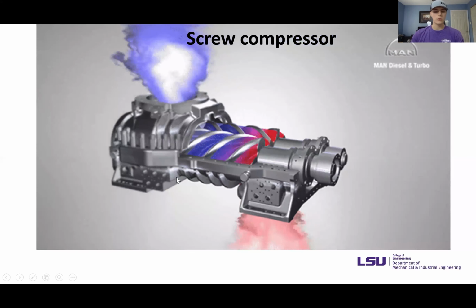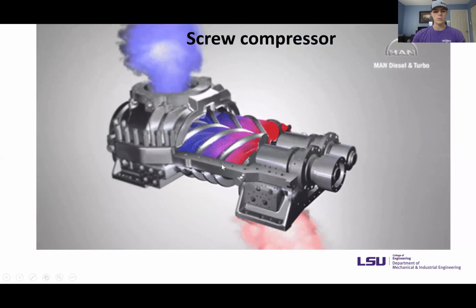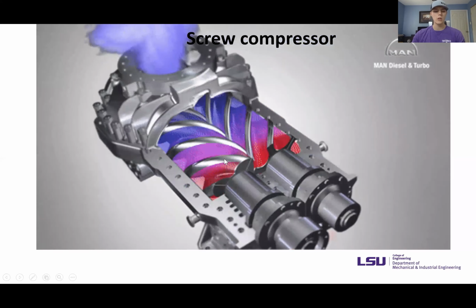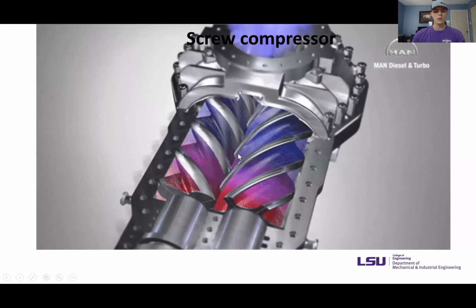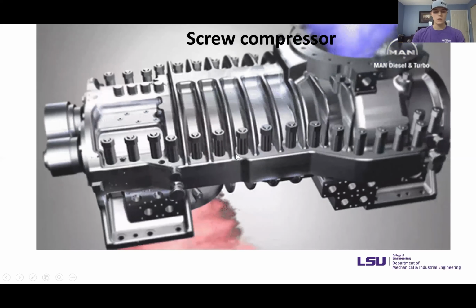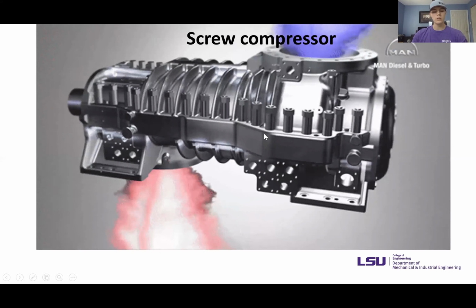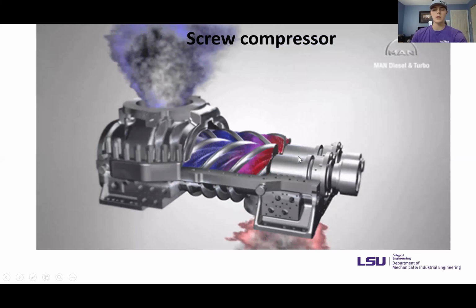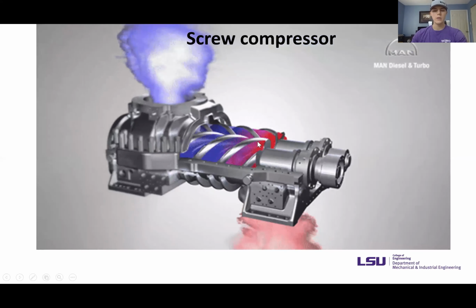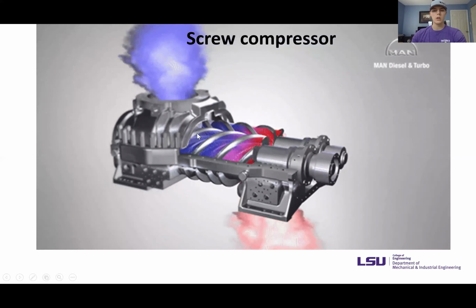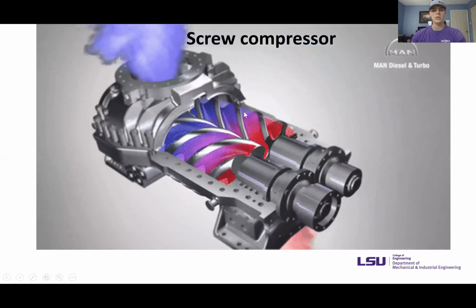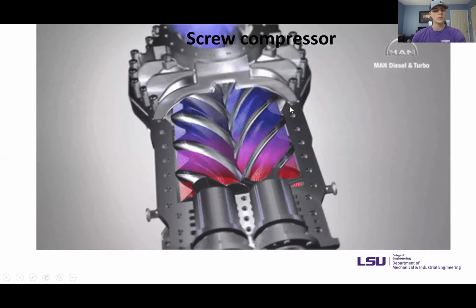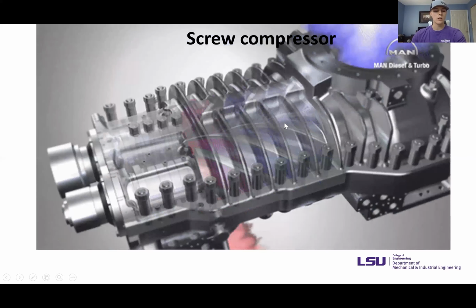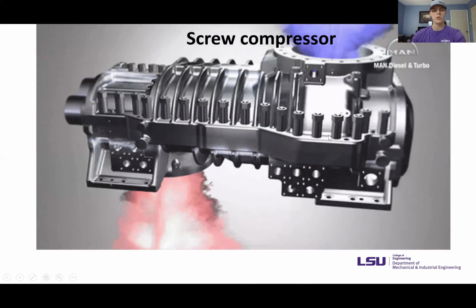Usually the male rotor is connected to the electric motor acting as the driving rotor, while the female rotor is driven by the male rotor. So only one of them is actually connected to the motor. Now these types of compressors are really useful because they have a high efficiency and high coefficient of performance, and they function more efficiently while operating for long periods of time.